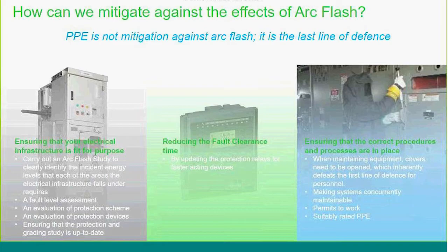Try and reduce the fault clearance time. So this goes against discrimination and grading now. What you're interested in is for certain faults trying to get a much faster clearance time. So there may be a compromise. If you have a particularly high risk at a substation, you may have to reduce your discrimination to make sure that substation faults are cleared in a much quicker time. Or implement protection schemes that help you whilst you're in that substation, maybe, to reduce the discrimination.